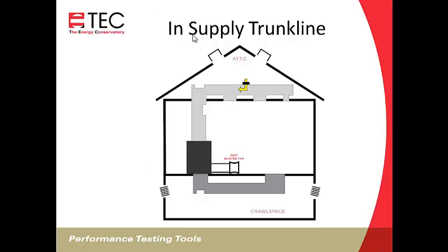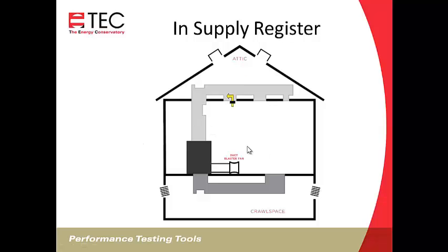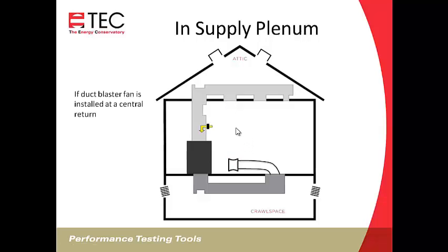So we're showing a static pressure probe pointing into the airflow. We're pressurizing with the duct blaster in this case. We're pointed into the airflow, and we're measuring at the supply trunk line. So that's one of the three locations where you can measure it, in that supply trunk line. Another location is one of the supply registers.